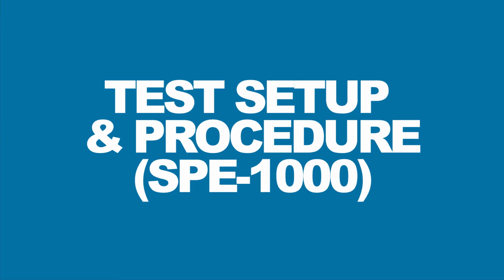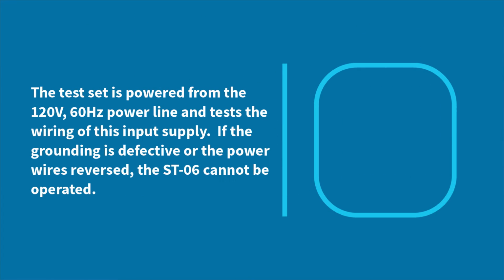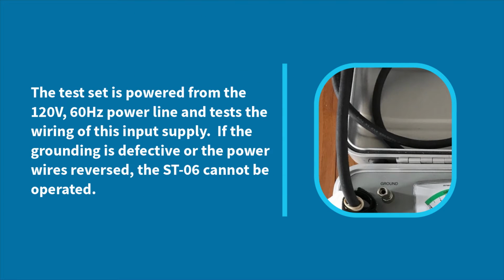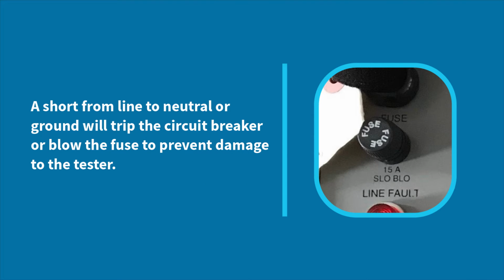Test setup and procedure, SPE 1000. The test is powered from 120 volts 60 Hz power line and tests the wiring of this input supply. If the grounding is defective or the power wires reversed, the ST06 cannot be operated. A short from the line to neutral or ground will trip the circuit breaker or blow the fuse to prevent damage to the tester.